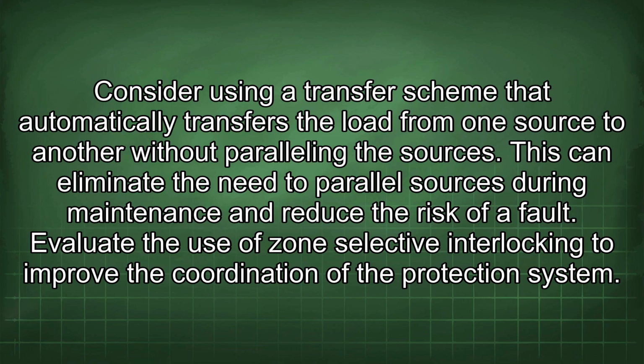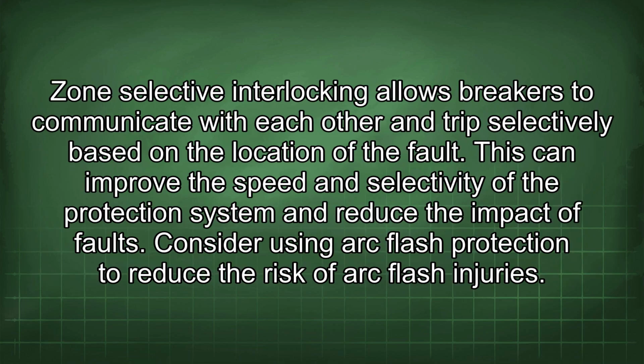Evaluate the use of zone-selective interlocking to improve the coordination of the protection system. Zone-selective interlocking allows breakers to communicate with each other and trip selectively based on the location of the fault. This can improve the speed and selectivity of the protection system and reduce the impact of faults.